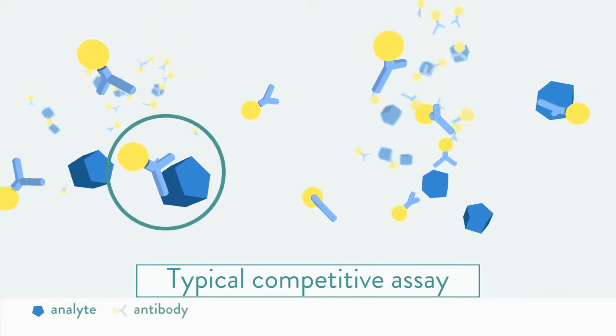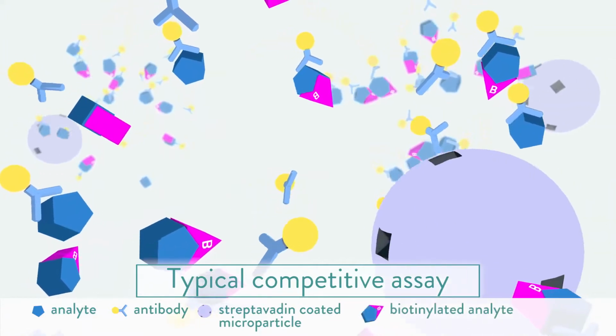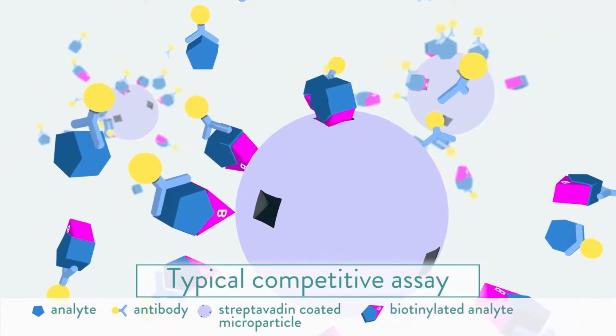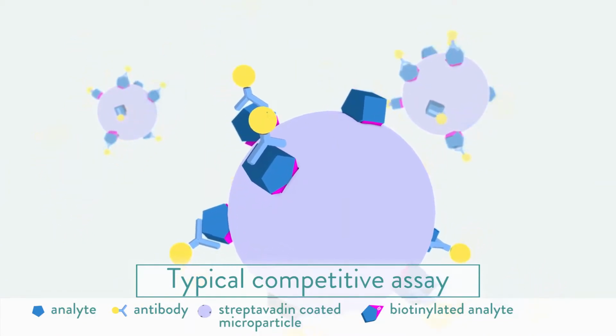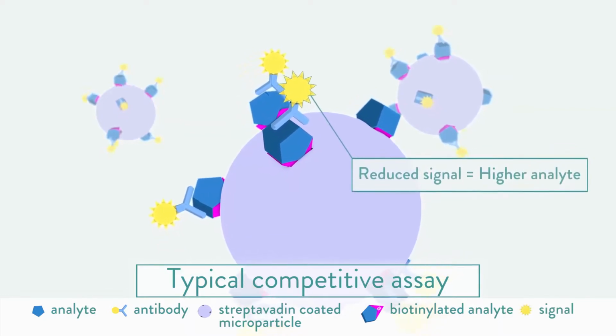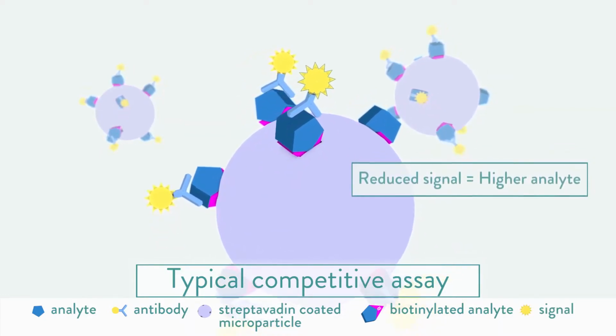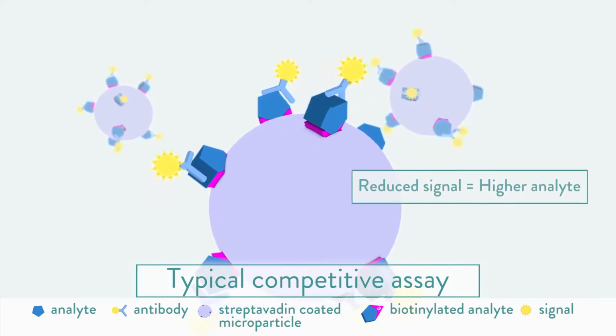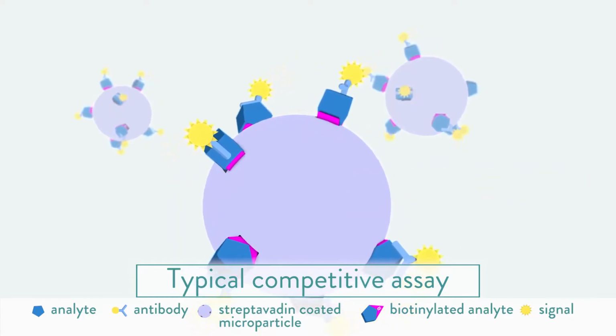Competitive immunoassays work differently. The free analyte in a sample first forms a complex with antibodies, then Streptavidin-coated microparticles and more biotinylated analyte are added. The antibody biotinylated analyte complex is captured by Streptavidin-coated microparticles, and following washing steps, a signal is generated from the bound labeled antibody. This time, a low signal corresponds to a high analyte concentration in the sample. This is because the free analyte in a sample directly competes with the biotinylated analyte that produces a signal. There is an inverse relationship between the signal and the analyte concentration.